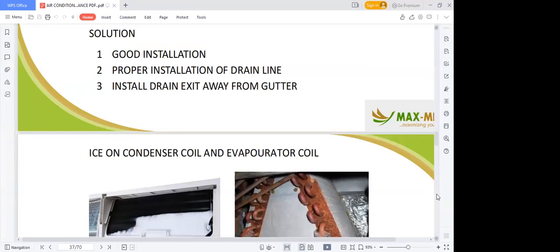Good installation, proper installation of the drain line. They install the drain exit away from the gutter. Don't install it, maybe in a central system, where your drain line is porting directly into the gutter and there's no U-trap. So the smell follows the drain back into your building.